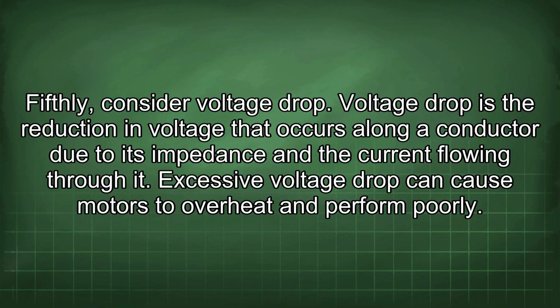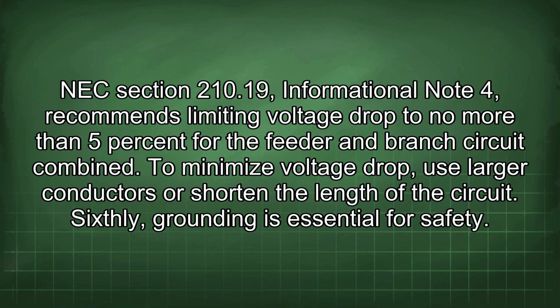Voltage drop is the reduction in voltage that occurs along a conductor due to its impedance and the current flowing through it. Excessive voltage drop can cause motors to overheat and perform poorly. NEC Section 210.19, Informational Note 4, recommends limiting voltage drop to no more than 5% for the feeder and branch circuit combined. To minimize voltage drop, use larger conductors or shorten the length of the circuit.